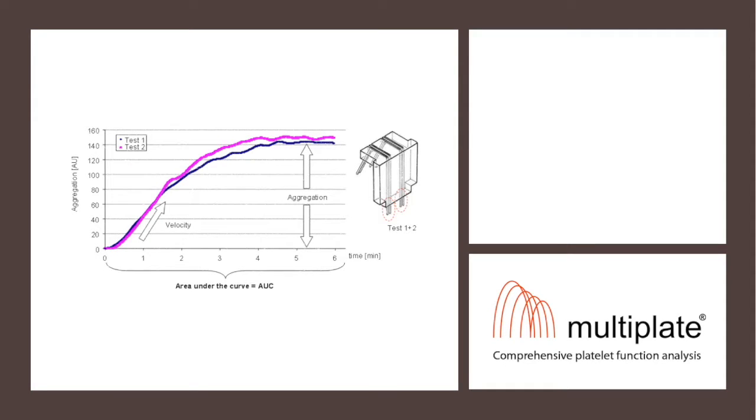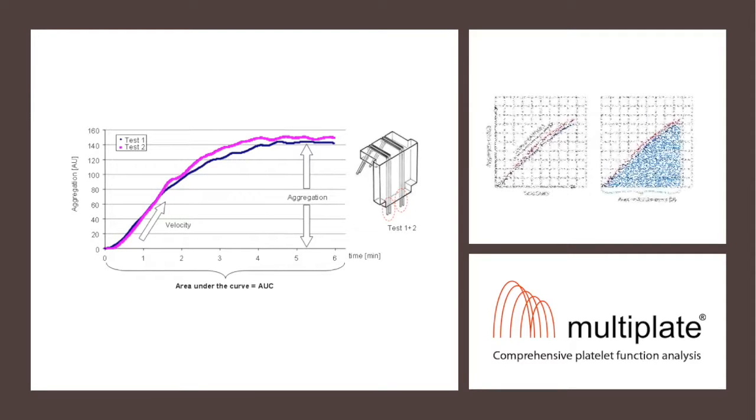The results are expressed by the values referred to as the area under the curve, or aggregation units. The duplicate sensor wires allow for automated quality control of measurements by comparison of the two simultaneously recorded results.